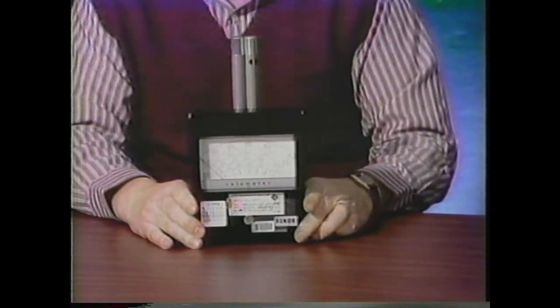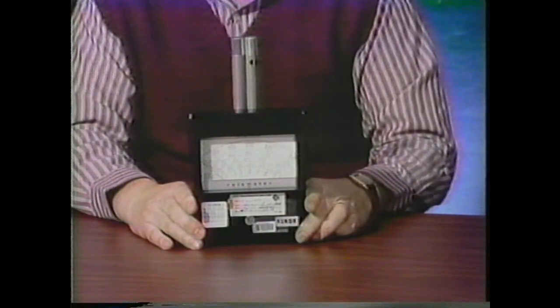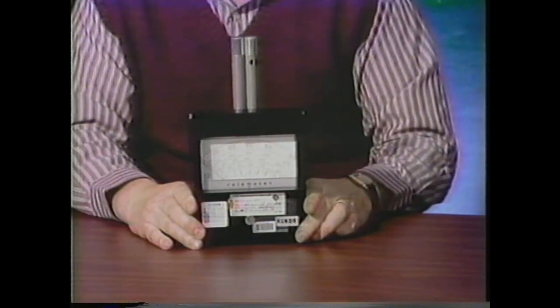Airflow measurements are displayed on this direct reading device when velocity pressure is exerted on a swinging vane located in the device. The velometer is capable of measuring 30 to 300 feet per minute with the low flow probe attached. The accuracy of the device is plus or minus 2%. Now the probe fits directly over two fittings in the back of the velometer. It can only be attached one way, with the arrow on the probe pointing to the left when looking at the front of the device. If the device is used in heavily contaminated environments, the accuracy of the device may be affected. The velometer is also calibrated by the Cincinnati lab every 2 years.